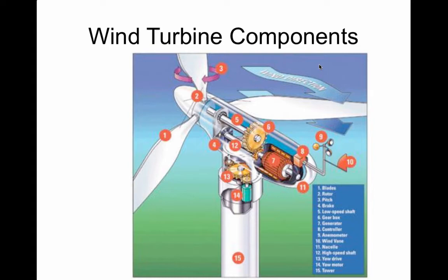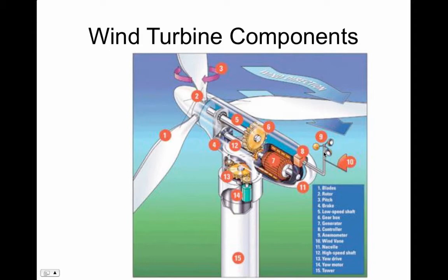Larger wind turbines are a little more complex. Here's a big wind turbine — the blades spin pretty slowly, and you have to have a gearbox because the generator spins at a faster speed. Small wind turbines spin pretty fast so you can just have them be direct drive. Actually they also make big wind turbines that are direct drive and eliminate the gearbox. Down here you've got gears that spin the wind turbine around to face the wind. This is an anemometer — a wind speed measuring device — used by the control system to know when to start the wind turbine up and when to shut it off.